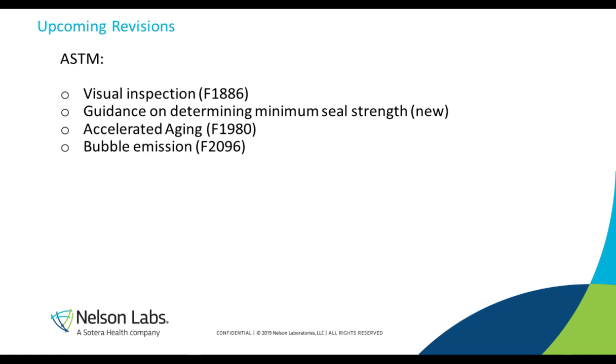So here's a summary slide of some of the upcoming revisions. The visual inspection, so this is your bonus. The visual inspection for F1886 is currently being revised. They're looking at bringing some of the annex items into the actual document as required inspection points. Currently, the only required inspection point is to look for channels. We're hoping to bring in possible tears and punctures if that is balloted and approved.